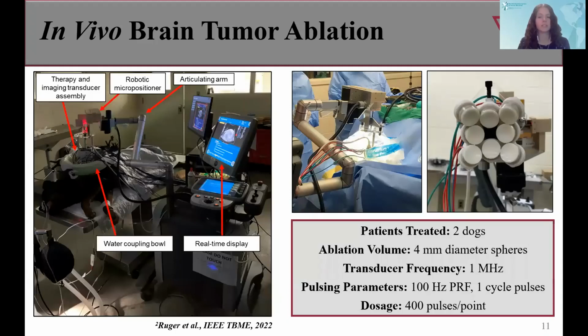2 dogs with spontaneous meningiomas were enrolled in this study and treated with the histotripsy system shown on the left and the 1 megahertz transducer shown on the right with a coaxially aligned ultrasound imaging probe. Notably, the transducer used in the in vivo experiments was the same array transducer used for the implant tests. 4 millimeter diameter spheres were targeted within the patient tumors and treated with single cycle histotripsy pulses applied at a pulse repetition frequency of 100 Hz and a treatment dosage of 400 pulses per point.